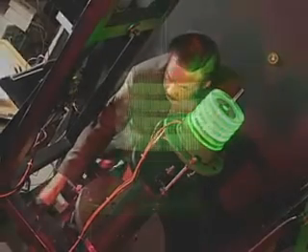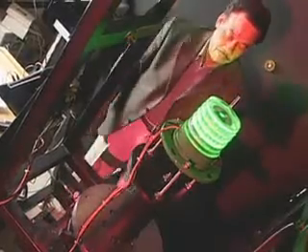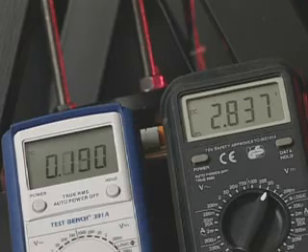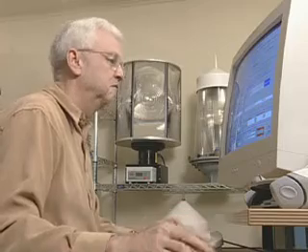To perform a full scan of an omnidirectional light, the light is mounted on the goniometer table with the optic plane of the lens passing through the horizontal axis of rotation and the light leveled and oriented. As power is applied, input voltage and current is monitored with precision digital meters. Key descriptive information is entered into the computer to become part of the record.